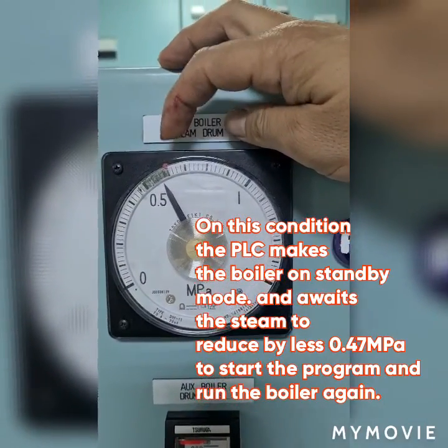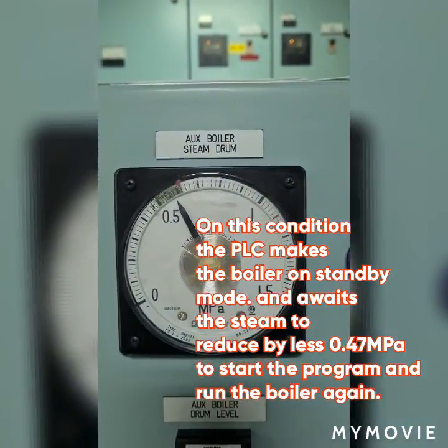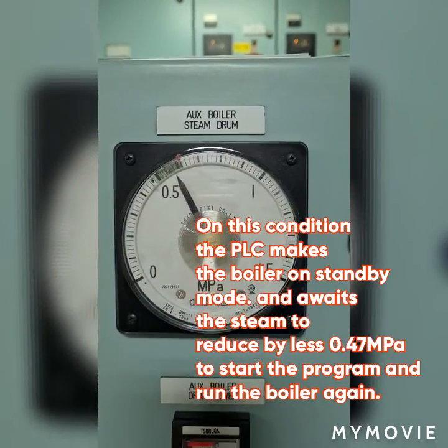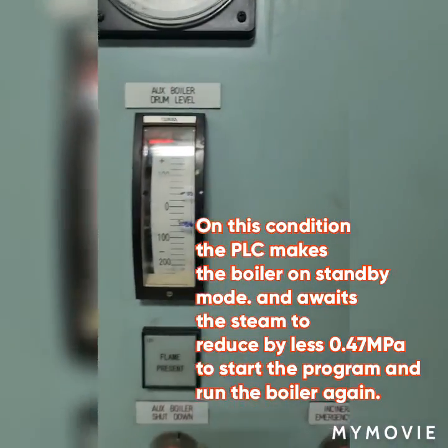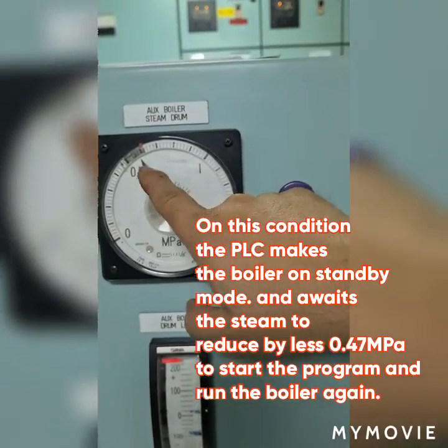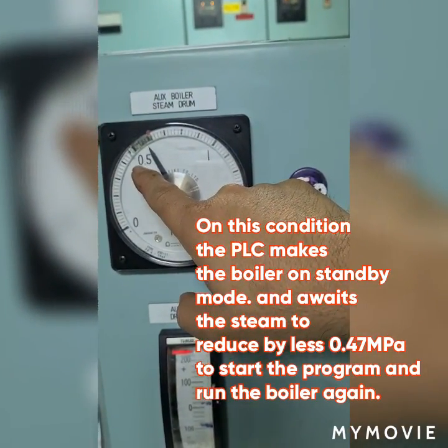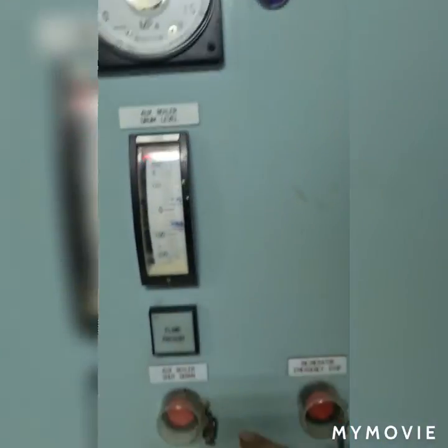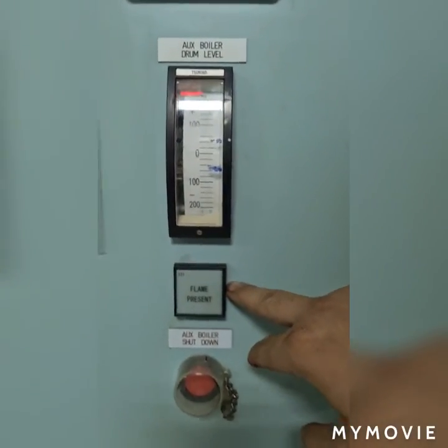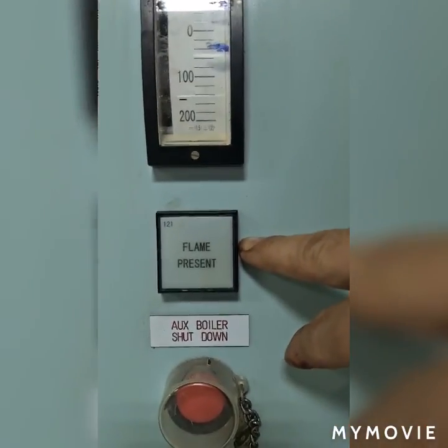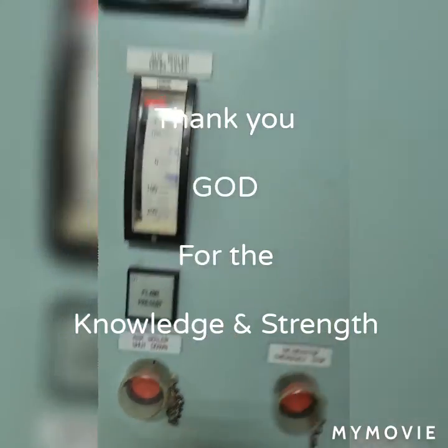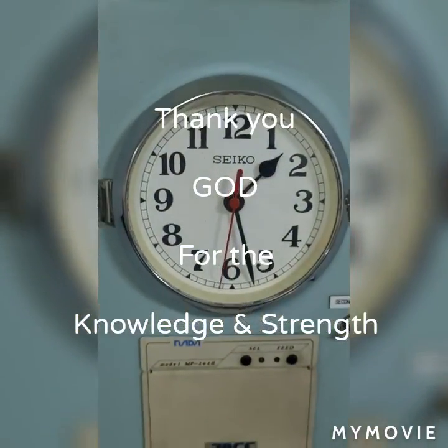Now we are observing the pressure being lowered from 0.62 to 0.58, and now we are going to wait until the pressure drops to 0.47, and this flame present will be activated if the boiler starts again.